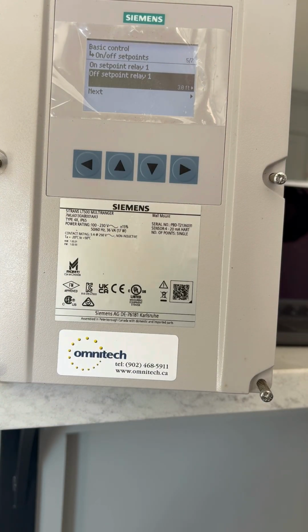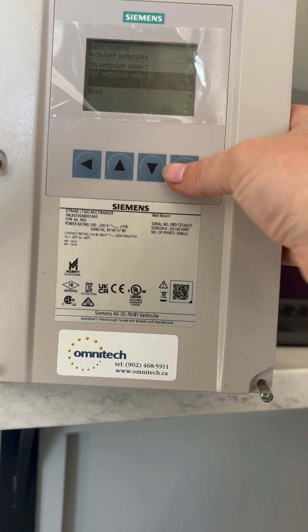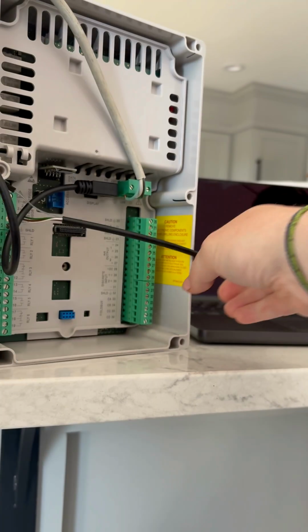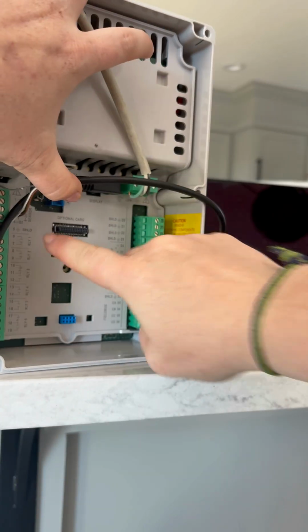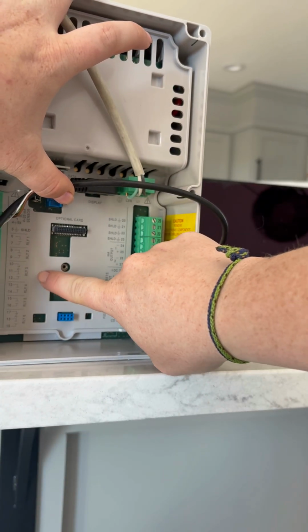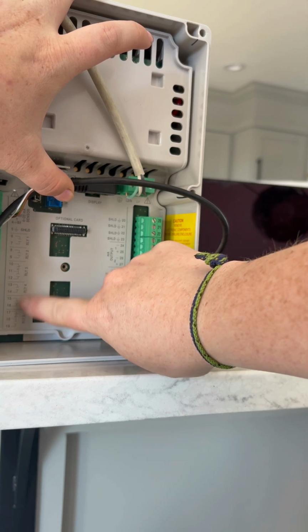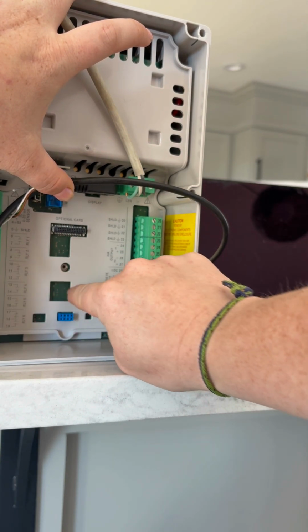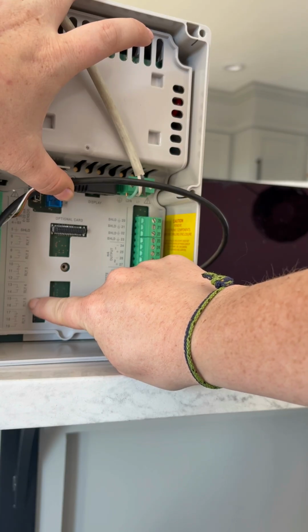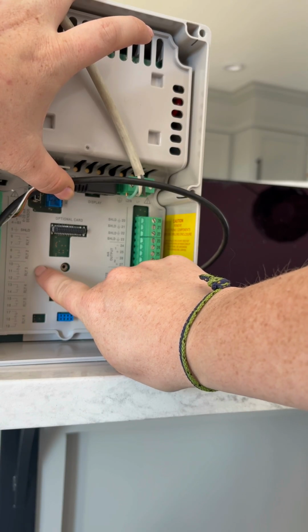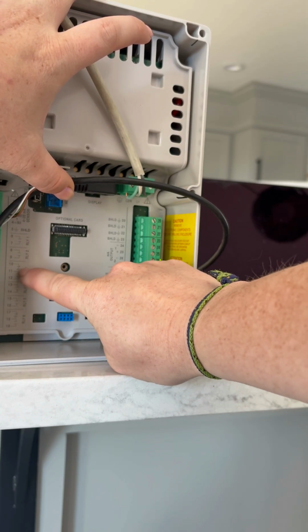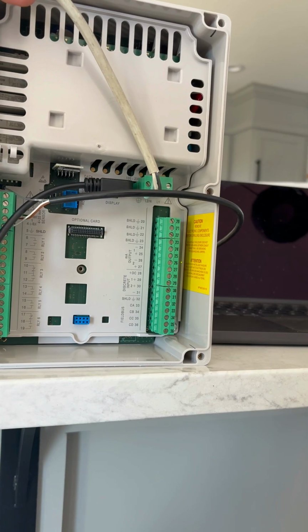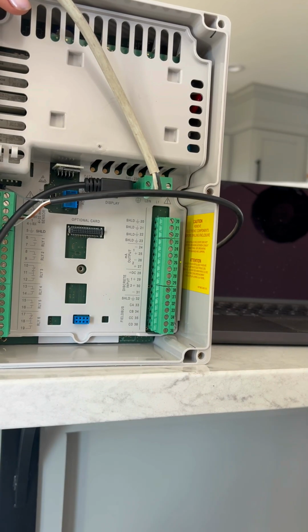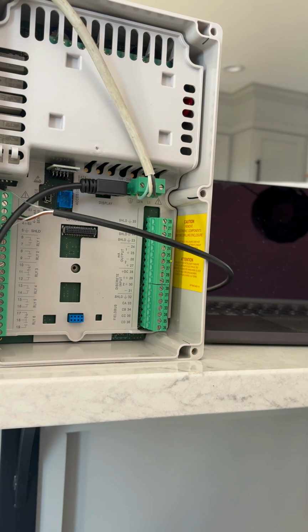So the valve itself is a normally closed valve. And so the relay here is normally open. Basically, and again, the relays, you can take a look at the wiring in here. You can see 1, 2, and then 3, 4, 5, and 6. You can wire them all normally open. 1, 2, and 4, 5, they are always normally open. That's just how it's wired. But you have an option for relay 3 and for relay 6 if you want to wire it normally closed. In this case, we want it to be normally open so that the solenoid on the valve is not activated, and when it is activated, it would then open that valve. I know that there's a couple different things going on there, and I can draw out a little schematic diagram if anyone needs it, but that should make sense.